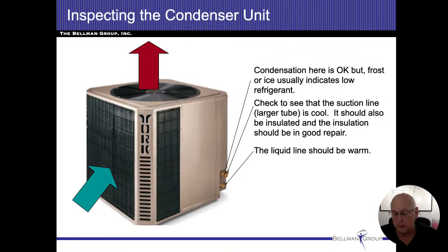Sometimes there's insulation that's wrapped around that pipe as well, and that insulation gets deteriorated by the ultraviolet rays of the sun. The whole purpose of the insulation is to prevent the condensation. But if it's outside and it's just condensating and dripping on the ground, I don't really see that as a problem, and I don't really make a comment on it.